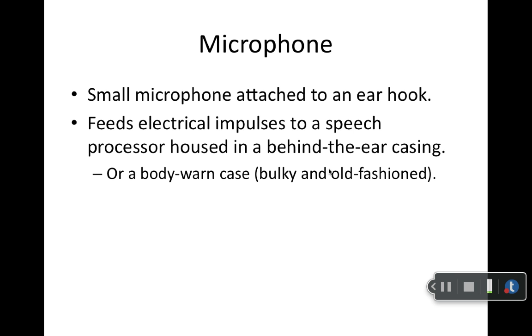There's a small microphone that sits on top of the pinna. It feeds the electrical impulses through a speech processor behind the ear. The speech processor is coded. It is delivered to a transmitter, which converts it to magnetic impulses, not radio, magnetic impulses, transmitted across the scalp into the electrode array. The electrical signal is sent up through to the cochlea. The cochlea, there it fires. It says, forget the outer hair cells. We'll just fire to the auditory nerve ourselves.